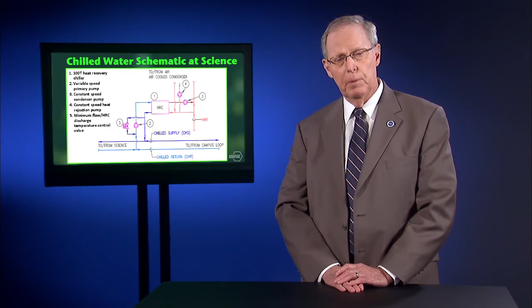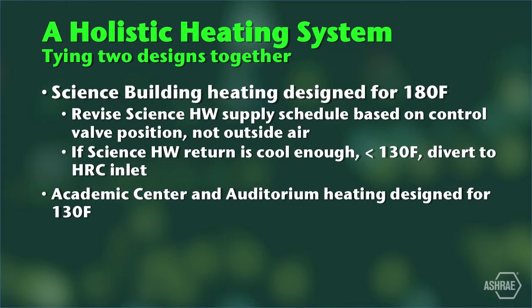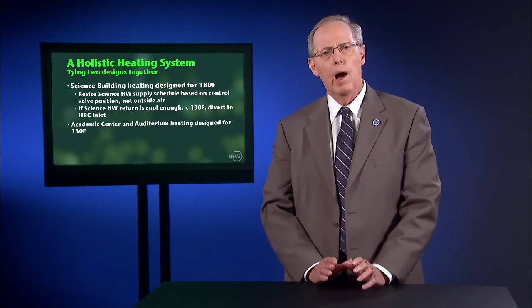The science building had been designed for 180-degree heating water. The other two buildings were being designed for 130-degree heating water, both reset based on outside air. Here's a good question. How hot does the heating water at science need to be? Well, it varies, but we would know that if we looked at the control valve position. We want to run the science heating system at the minimum temperature that would maintain the building. It doesn't have to be 180 very often, and if no hot water control valve is more than 90% open, then the water is hot enough.